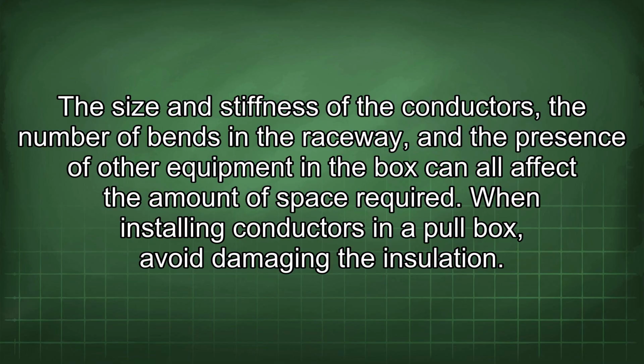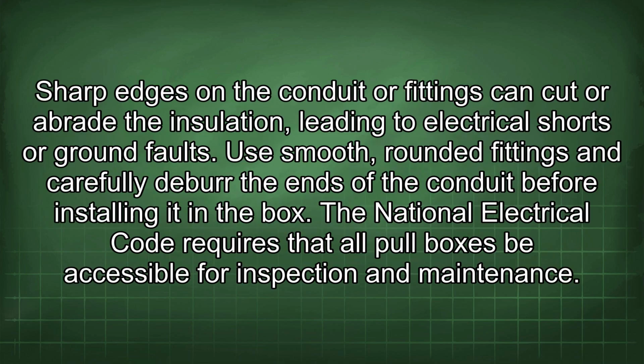When installing conductors in a pull box, avoid damaging the insulation. Sharp edges on the conduit or fittings can cut or abrade the insulation, leading to electrical shorts or ground faults. Use smooth, rounded fittings and carefully deburr the ends of the conduit before installing it in the box.